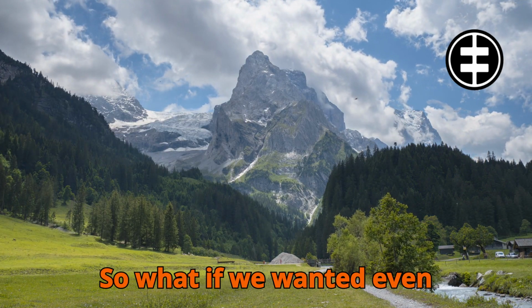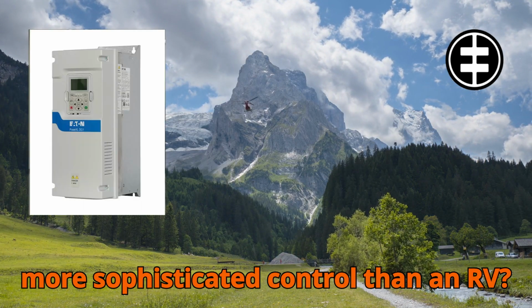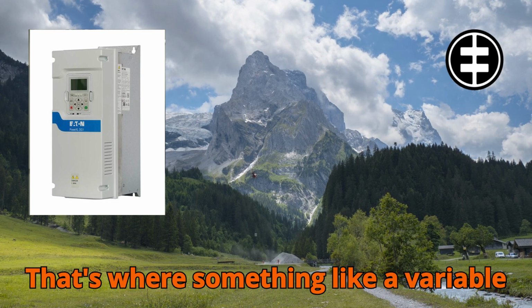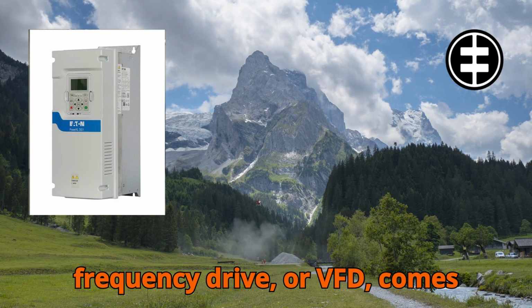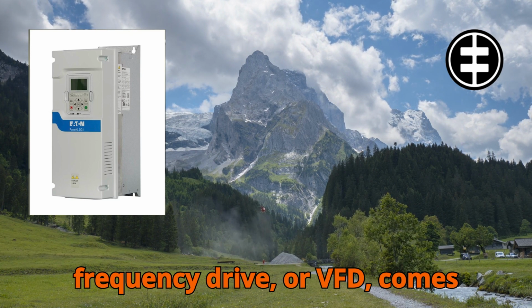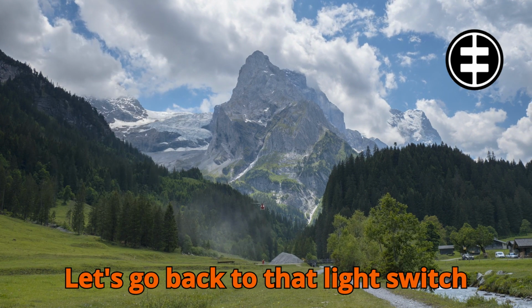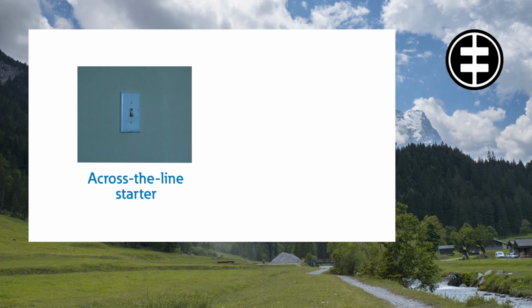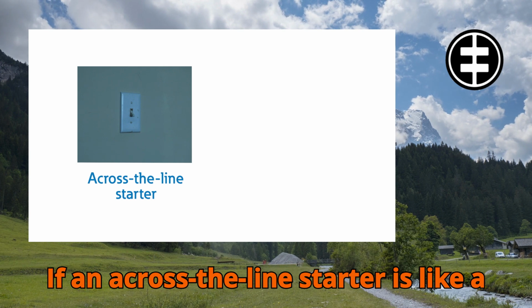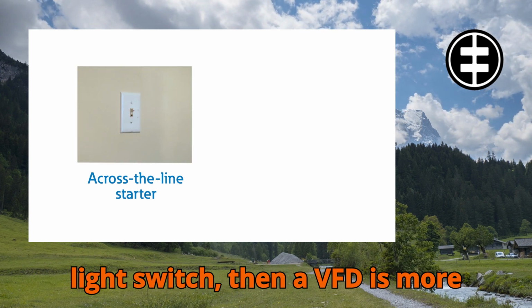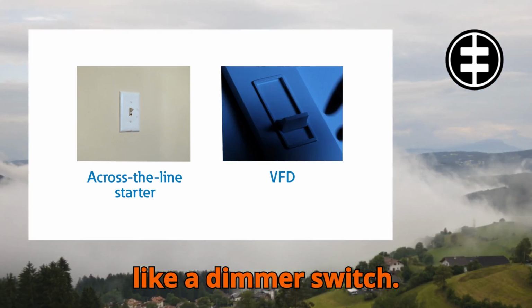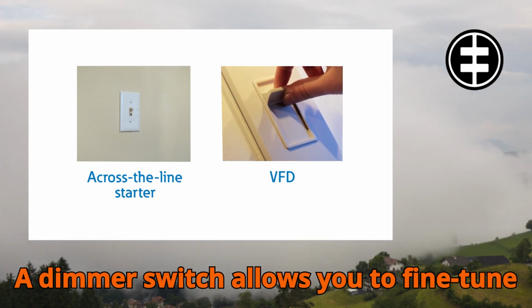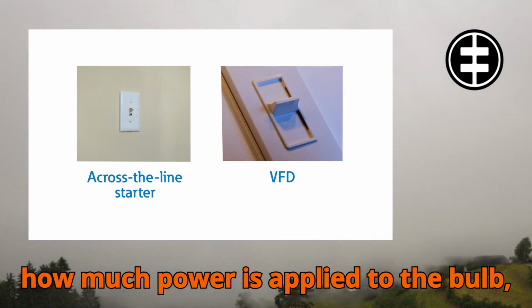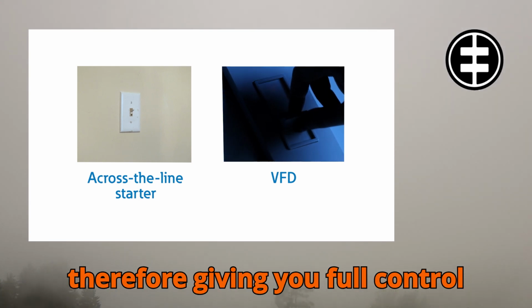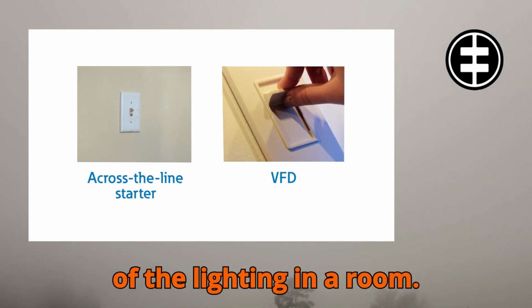So, what if we wanted even more sophisticated control than an RVSS? That's where something like a variable frequency drive, or VFD, comes in. Let's go back to that light switch analogy. If an across-the-line starter is like a light switch, then a VFD is more like a dimmer switch. A dimmer switch allows you to fine-tune how much power is applied to the bulb, therefore giving you full control of the lighting in a room.